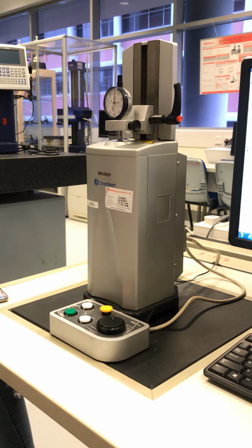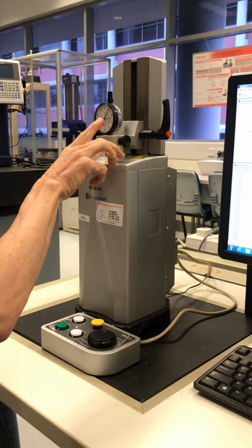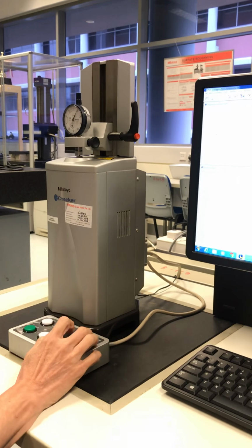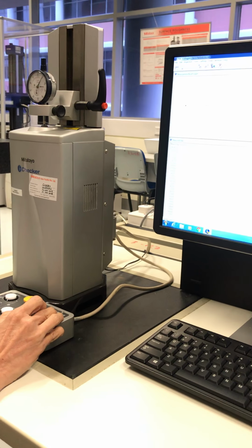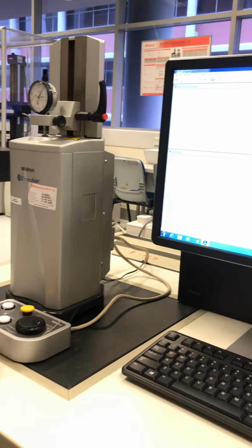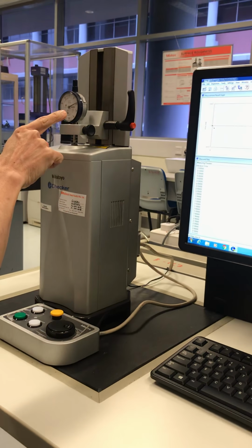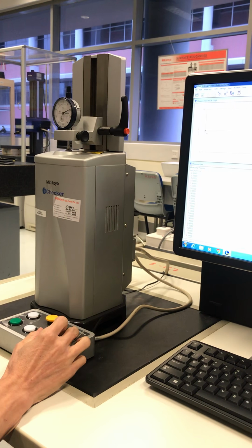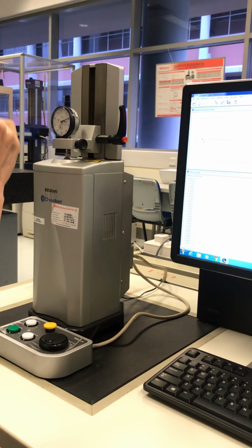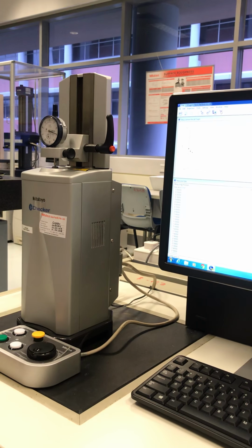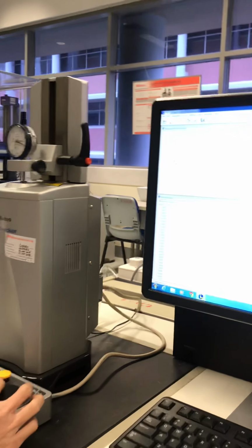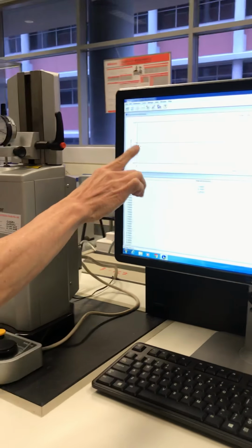Here, start is here. Data correction start. Already set to 0, right? Here 0. Then you move very close to 0.1. You can see the next reading is 0.1. So you adjust perfectly to 0.1. See here, when I add data in, you go to the next reading. Semi-auto. One division away from the calibration reading. And then you can plot, check that the plot is okay.